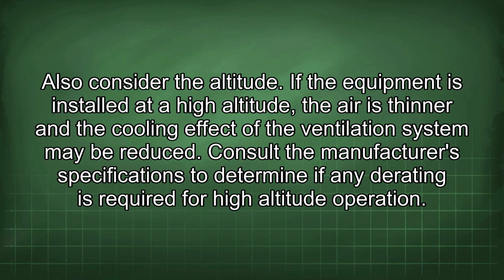Also consider the altitude. If the equipment is installed at a high altitude, the air is thinner and the cooling effect of the ventilation system may be reduced. Consult the manufacturer's specifications to determine if any derating is required for high altitude operation.